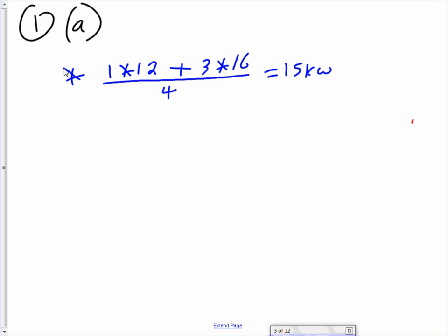This is coming from table 220.55, note number 2. If you guys go to the 220.55 table, note number 2 will tell you if they are more than 8 3/4, you average them and you increase the demand 5% for every kW the average is more than 12.